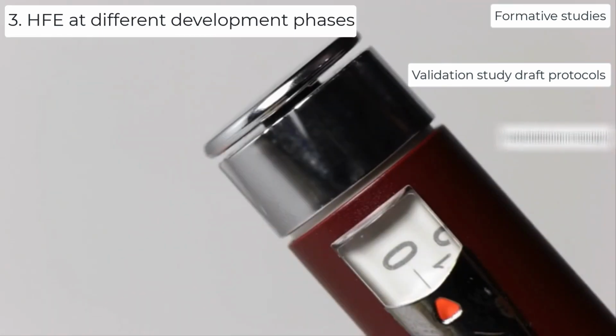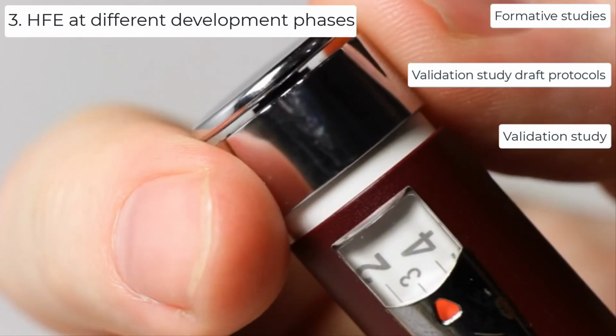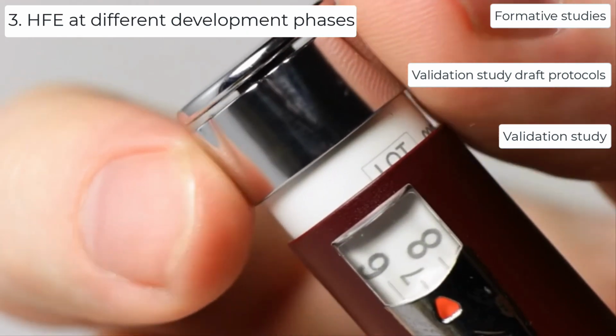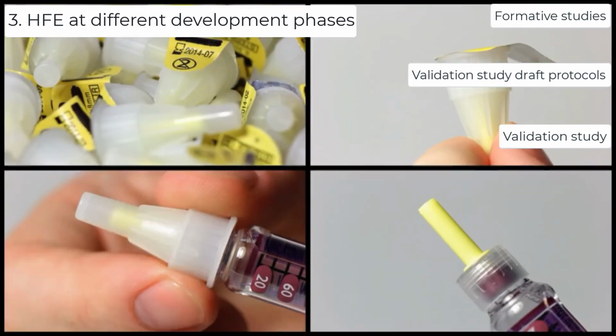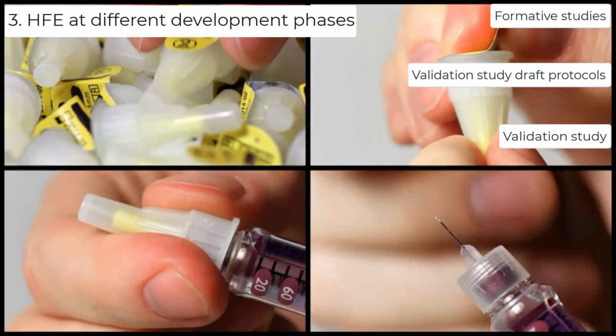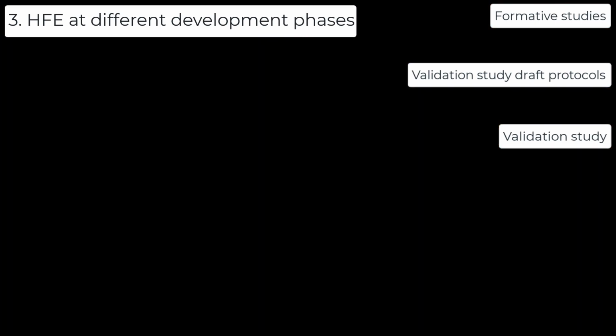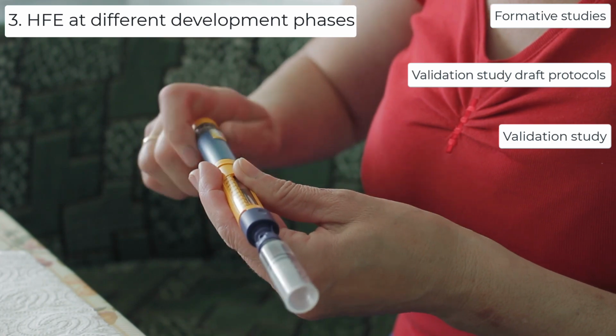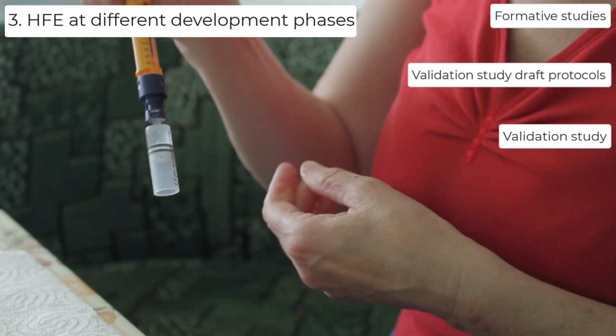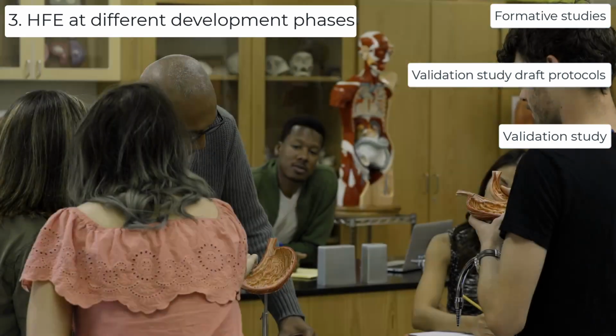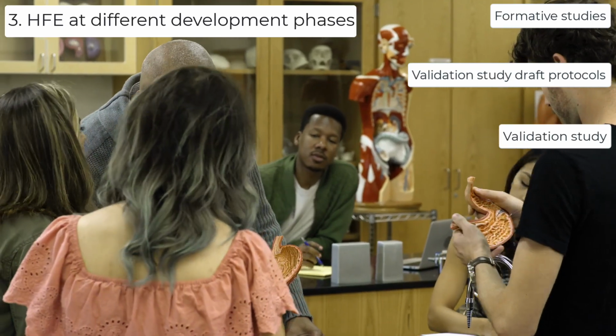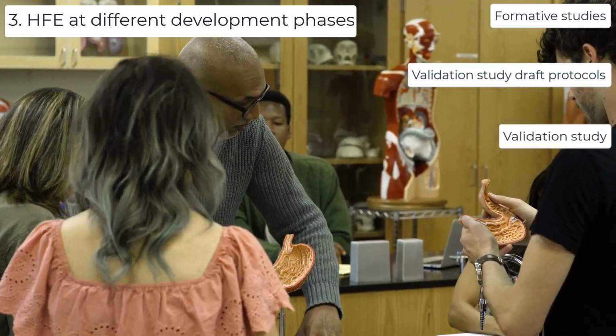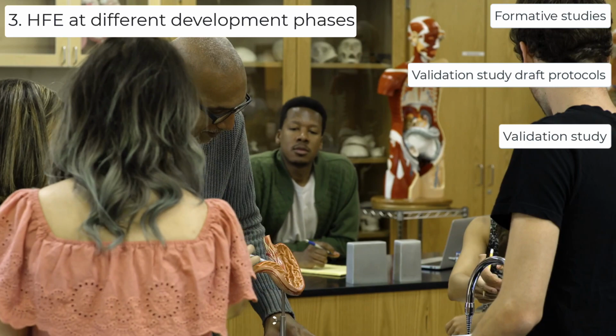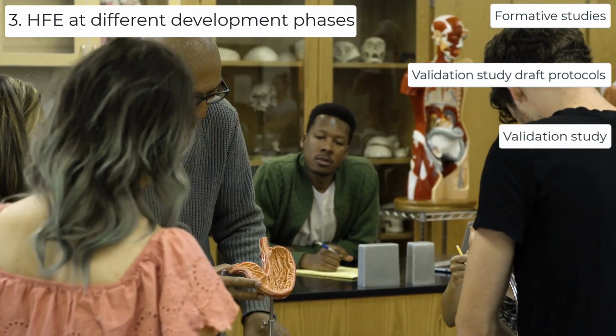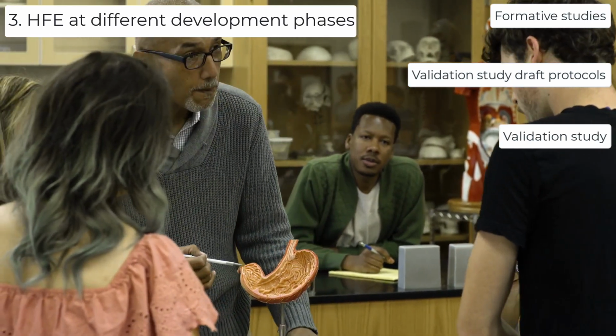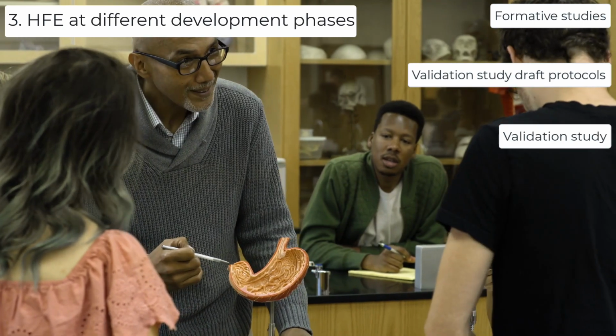The human factors validation study is conducted after finalizing the user interface design to ensure the safe and effective use of the product by its intended users in the expected environment. In some cases, if the final finished combination product is not ready, a representative test product might be used if justified. If training is included in the user interface design, it should be validated, including the training of trainers. Both trained and untrained users should be tested if training is optional or inconsistent, with the possibility of testing only untrained users in certain cases.